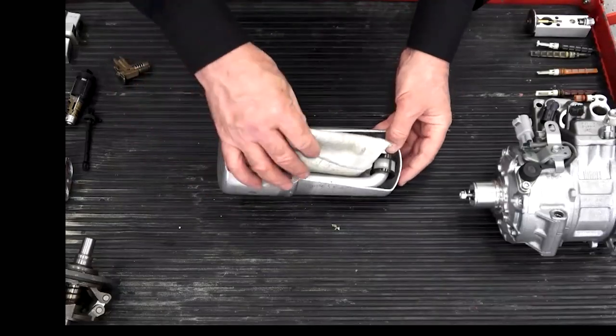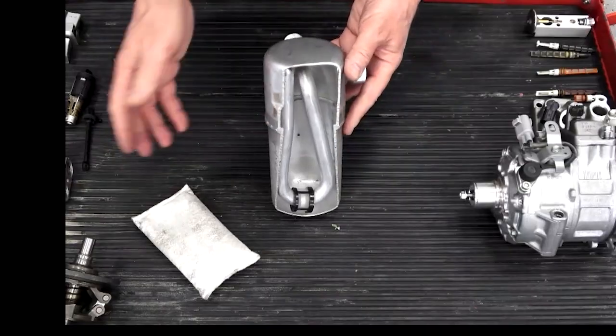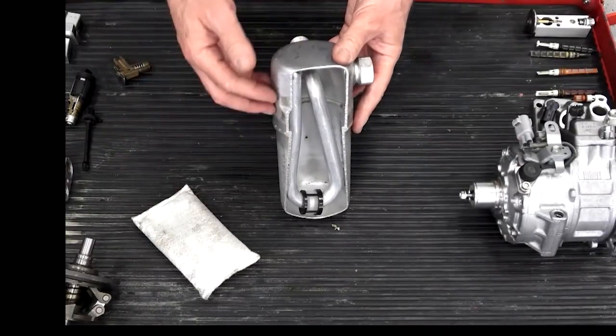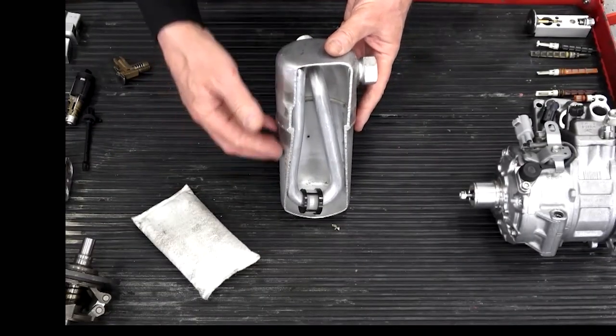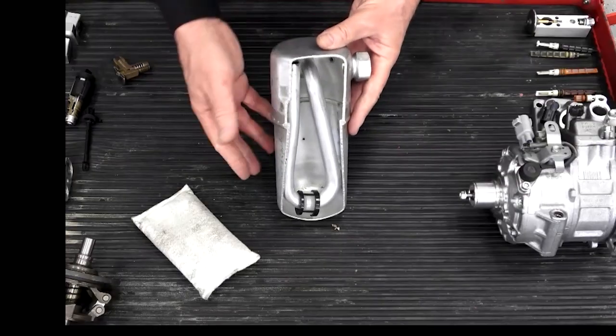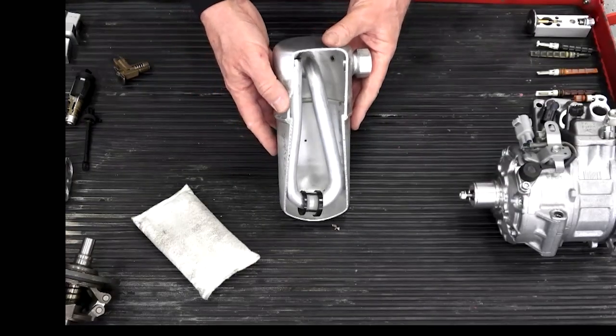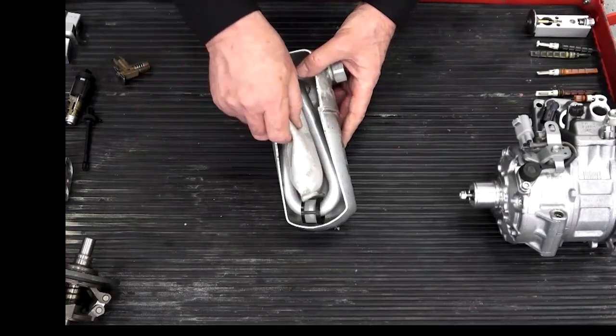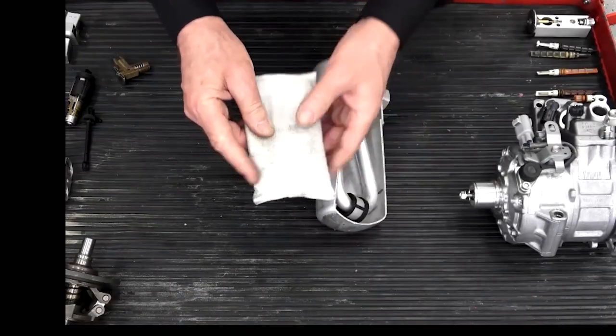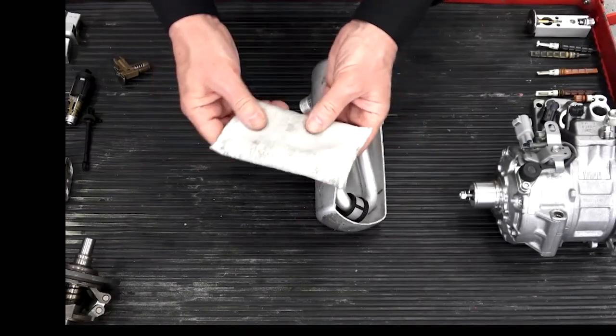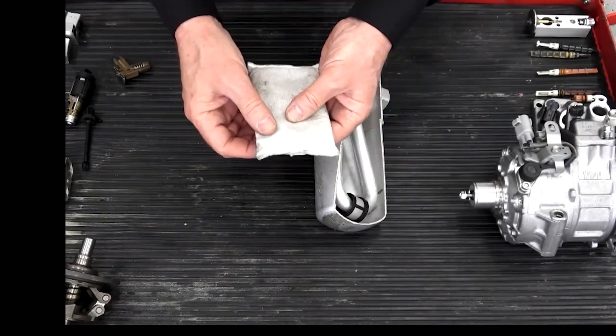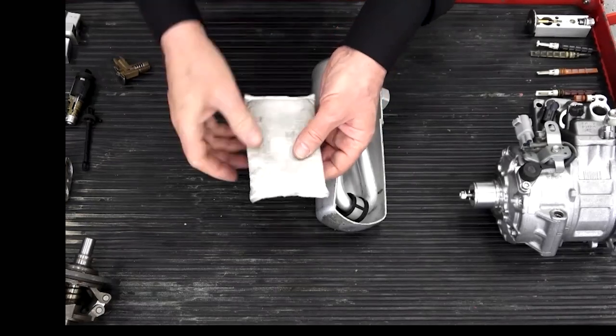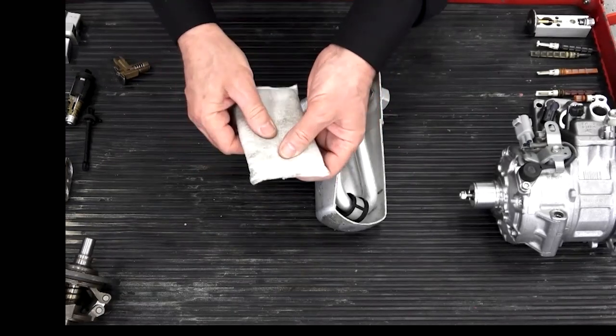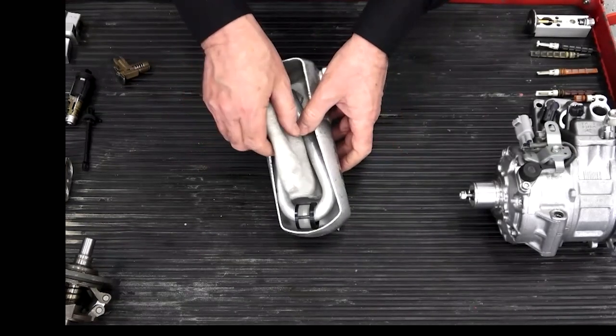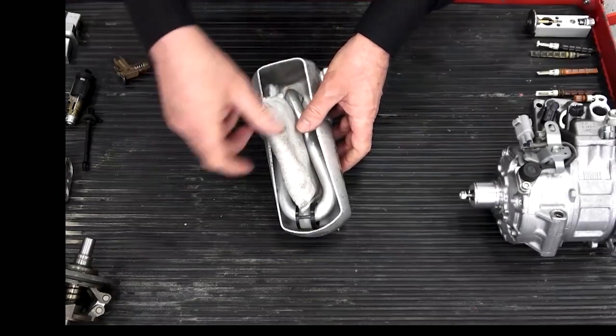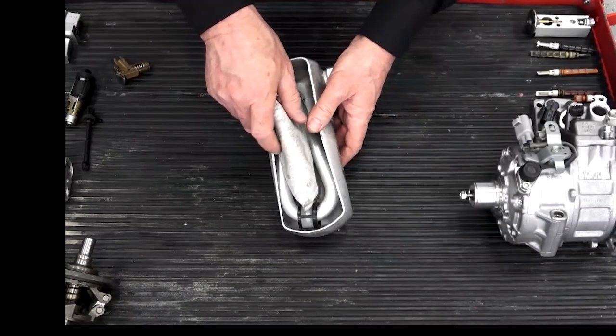So the accumulator performs 4 functions. It acts as a storage device, so there's a little bit of excess refrigerant to compensate for different heat loads in the system. It's kind of a storage tank, if you want to think about it like that. It's also got the desiccant medium. If we cut this open, it's full of beads inside, and it's a desiccant medium, XH7, XH9. It absorbs trace moisture from the system to prevent corrosion and acid buildup and so forth.